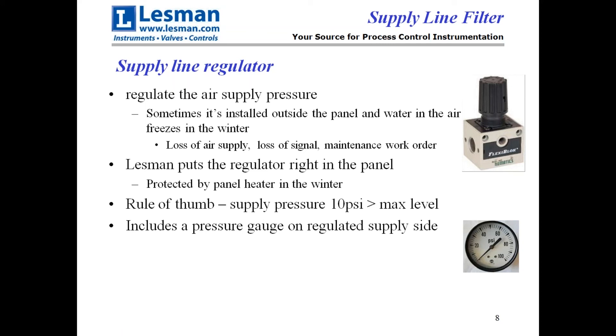The rule of thumb for supply pressure is you need 10 psi more than whatever the maximum level needs to force a bubble out of the dip tube. We put a pressure gauge on there so that anyone who opens the panel can read what the pressure on the supply side is.